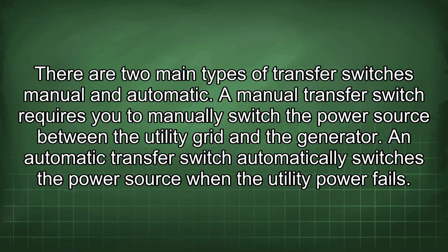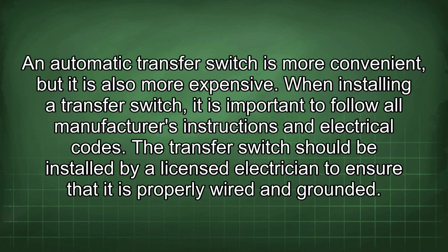There are two main types of transfer switches: manual and automatic. A manual transfer switch requires you to manually switch the power source between the utility grid and the generator. An automatic transfer switch automatically switches the power source when the utility power fails. An automatic transfer switch is more convenient, but it is also more expensive. When installing a transfer switch, it is important to follow all manufacturers' instructions and electrical codes. The transfer switch should be installed by a licensed electrician to ensure that it is properly wired and grounded.